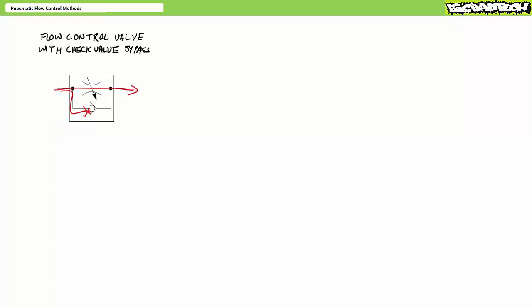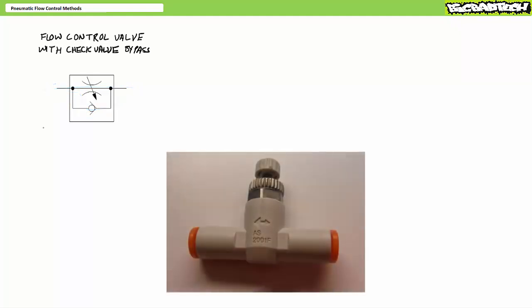In one direction, the check valve poppet is forced to the seat and forces flow through the restriction orifice. In the reverse direction, the check valve opens and allows unrestricted flow. Because flow control valves with check valve bypasses are orientation dependent, manufacturers often indicate direction of controlled flow using an arrow. Alternatively, one might see a big arrow pointing in the unrestricted direction and a small arrow pointing in the controlled direction. Install it in the wrong place and the wrong orientation and you'll get wrong results.